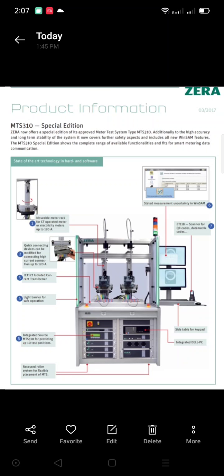From that, we are coming to the smart energy meter. Some additional tests can be performed by using our Zera 3-phase MTS310 equipment. The communication test, like the smart meter communication with its optical port and the RF communication port, can be tested, and the smart meter functionality for routine tests can be performed, and the burden test, tamper test, stress test, etc. can be performed by using our new 3-phase smart meter communication equipment. The voltage range is 10 volt to 500 volt and the current range is up to 120 ampere.